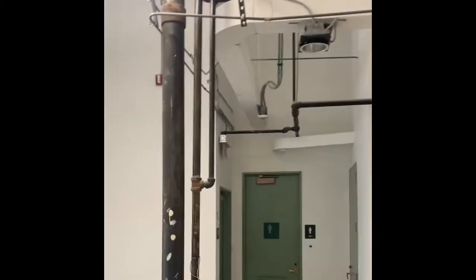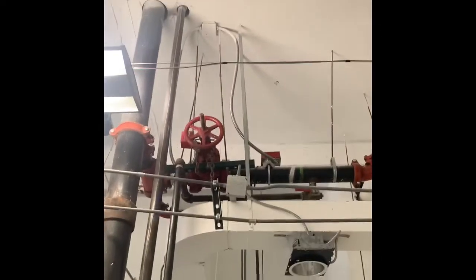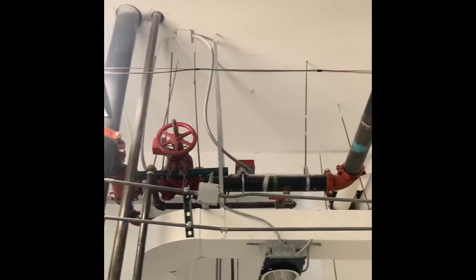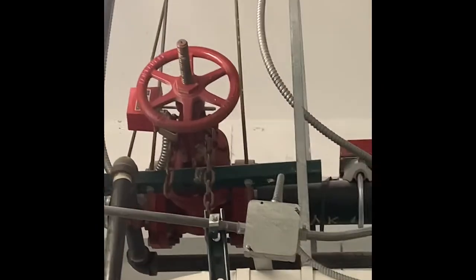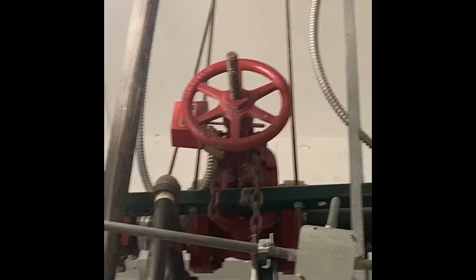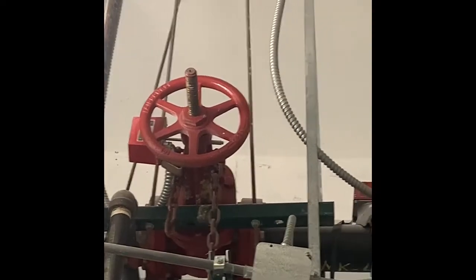Show you one of our standpipes for the sprinkler system. Control valve. Zoom in a little bit. OS&Y control valve, tamper switch connected to it. Right off the discharge side of that, you will see a flow switch to monitor if one of the heads on this system were to burst.